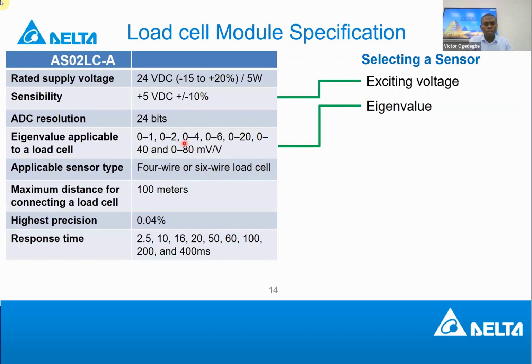So for our module, the maximum Eigenvalue we support is 80 millivolts, from 0 to 80 millivolts. For example, if you have a sensor that supports 100 millivolts, then you cannot use this. If you use it, the reading will not be accurate. So that's the Eigenvalue. It also helps you to select the correct sensor.